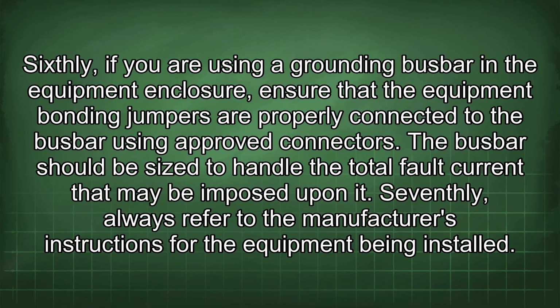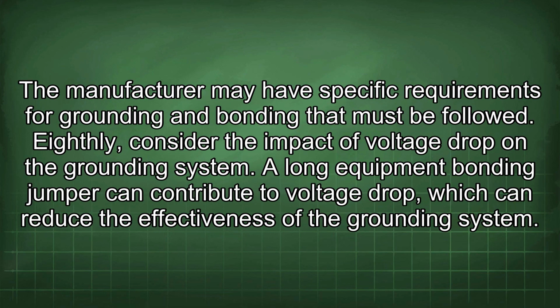Sixthly, if you are using a grounding busbar in the equipment enclosure, ensure that the equipment bonding jumpers are properly connected to the busbar using approved connectors. The busbar should be sized to handle the total fault current that may be imposed upon it. Seventhly, always refer to the manufacturer's instructions for the equipment being installed. The manufacturer may have specific requirements for grounding and bonding that must be followed.